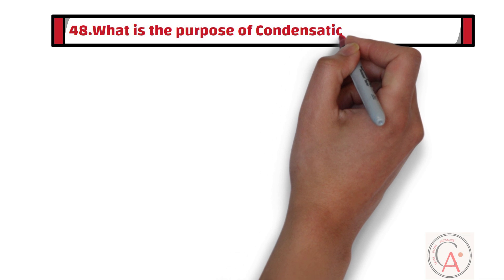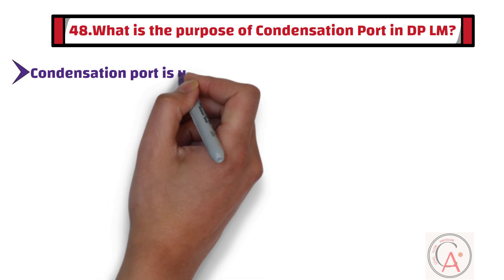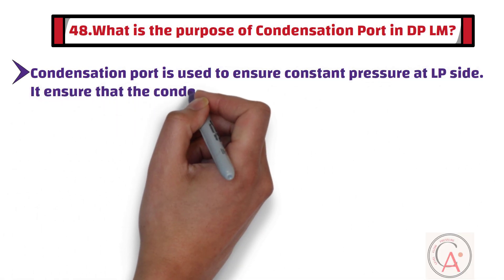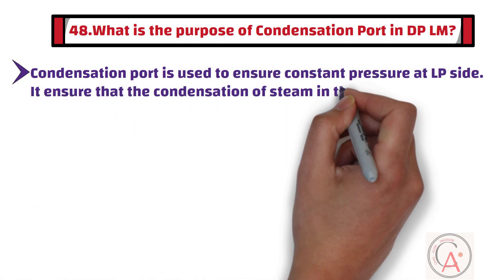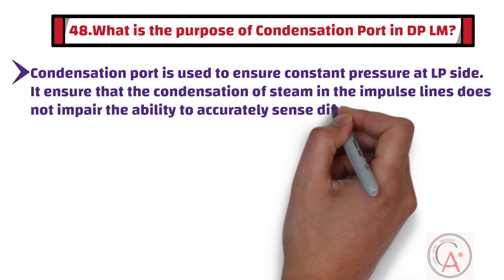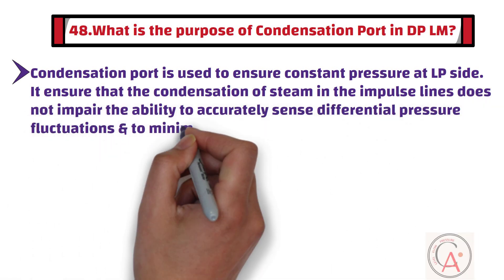Question 48: What is the purpose of a condensation port in DP level measurement? A condensation port is used to ensure constant pressure at the low pressure side. It ensures that the condensation of steam in the impulse lines does not impair the ability to accurately sense differential pressure fluctuations and minimize gauge line error.